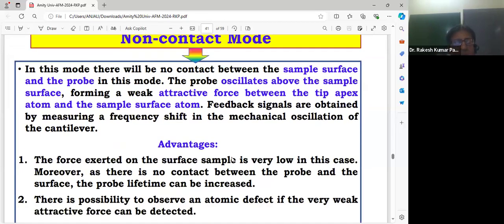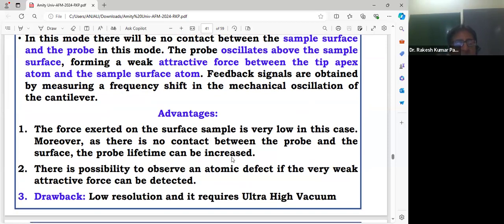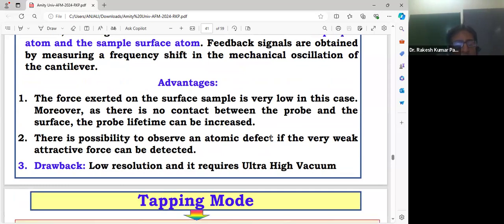Here the feedback signals are obtained by measuring a frequency shift in the mechanical oscillation of the cantilever. So what are the advantages and disadvantages of this mode? The force exerted on the sample surface is very low in this case. Moreover, as there is no contact between the probe and the surface, the probe lifetime can be increased. This is the advantage of non-contact mode, because there is no direct contact between the probe and the surface. So the lifespan of the cantilever and the tip can be enhanced. Another very important point is that there is a possibility in this mode to observe an atomic defect.